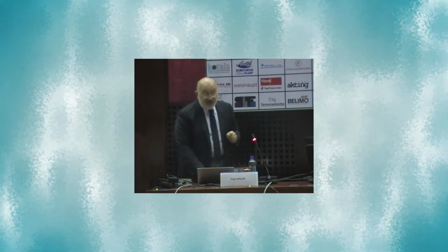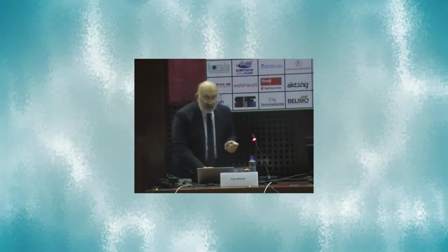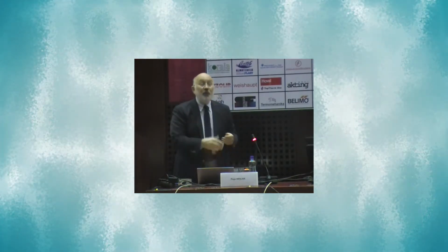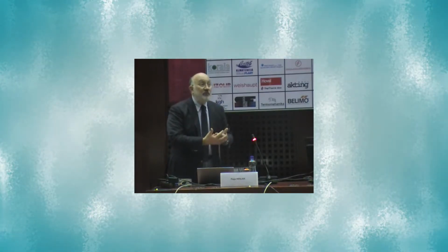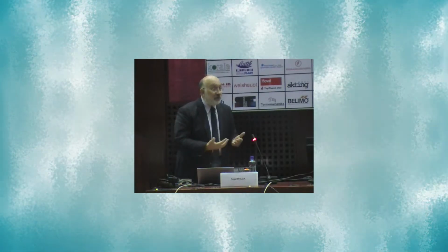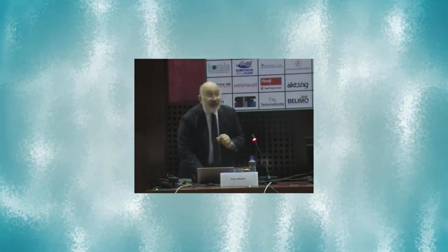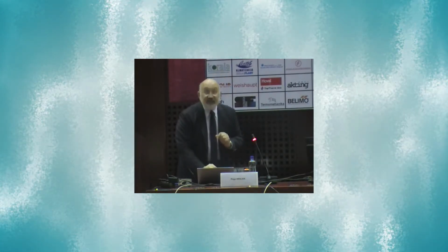But we didn't take this tube to take heat transfer measurements, we have expanded this tube with a mandrel as it would be expanded in a normal heat exchanger. In other words, when you push a mandrel, you deform the tips of the microfins, and you get something like this.